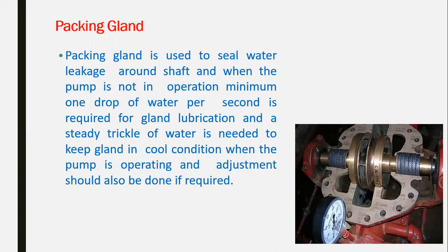Another device is a packing gland, and the packing gland is used on the shaft itself to seal the water around the shaft of the pump. So this packing gland normally requires lubrication, and its function is to avoid any leakage of water around the shaft of the pump. Depending on the pump size, during operation, in big and large pumps, due to the friction and the operation, it might require a cooling system for the shaft.